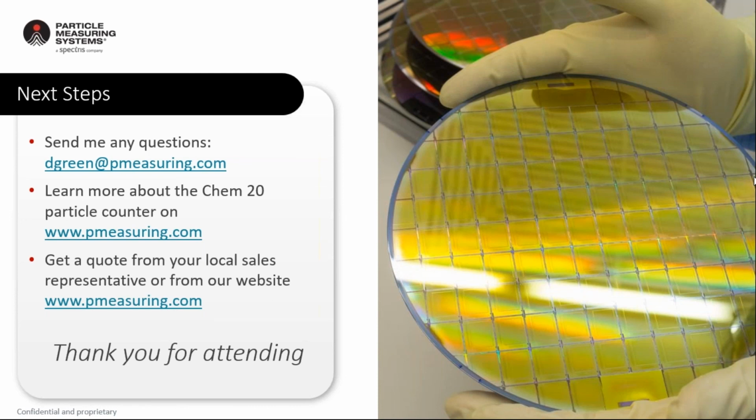We'd be happy to help you out with that, but the typical locations that people are going to measure are at the location where the chemical comes into the factory, in this case, where the tanker lorry is being unloaded into the storage tank. So you want to measure there to make sure that the chemical is really clean coming in. And then typically the location where the chemical goes out to the fab.